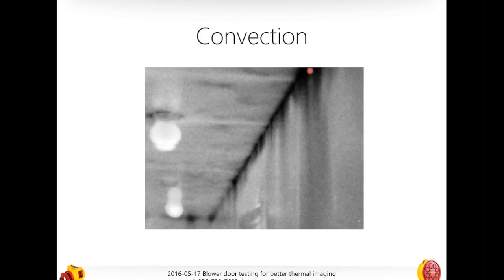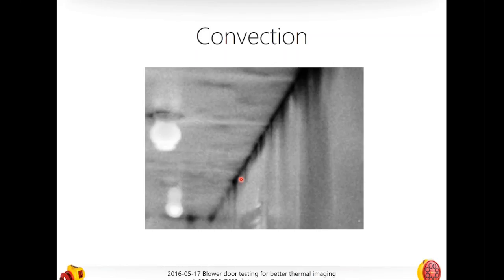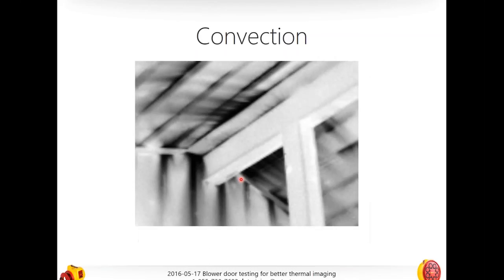Another great example — the difference between this picture, which has windows making it an outside wall, and this one, which is an interior hallway, but still has obvious leakage with the blower door running. The answer: it is an open top plate. We're looking at open top plates — one exterior, one interior — and it really doesn't make that big a difference when talking about convection. In fact it might even be worse on interior walls.